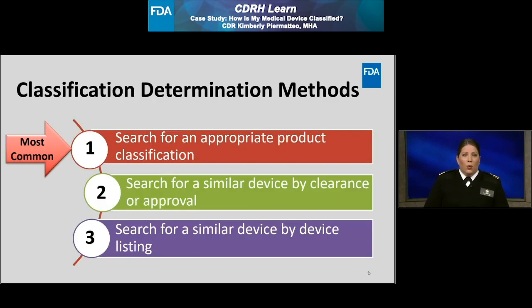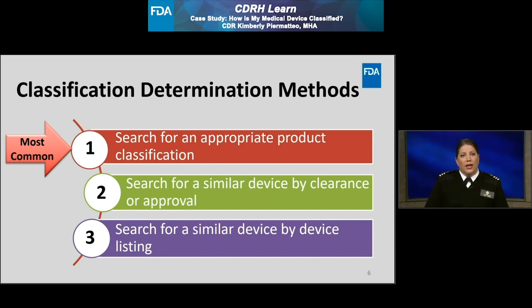When determining a device's product classification, there are three methods that I recommend. The first is to directly search for the appropriate product classification — I'll refer to this as method one, and this is the most common method used. A second method, or method two, is to search for a similar device by its clearance or approval. And lastly, method three is to search for a similar device by device listing. I'm going to walk through how to conduct each of these search methods over the next several slides.